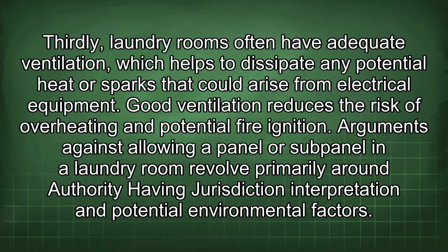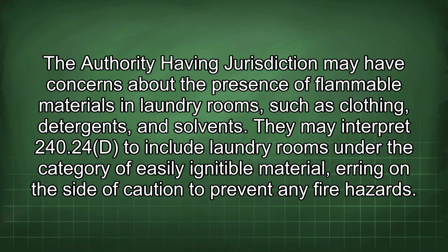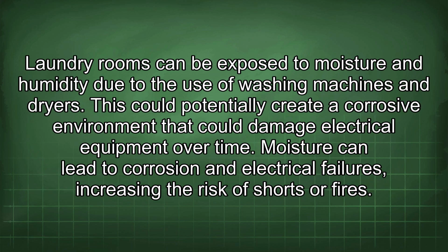Arguments against allowing a panel or subpanel in a laundry room revolve primarily around authority having jurisdiction interpretation and potential environmental factors. The authority having jurisdiction may have concerns about the presence of flammable materials in laundry rooms, such as clothing, detergents, and solvents. They may interpret 240.24(D) to include laundry rooms under the category of easily ignitable material, erring on the side of caution to prevent any fire hazards. Laundry rooms can be exposed to moisture and humidity due to the use of washing machines and dryers. This could potentially create a corrosive environment that could damage electrical equipment over time. Moisture can lead to corrosion and electrical failures, increasing the risk of shorts or fires.